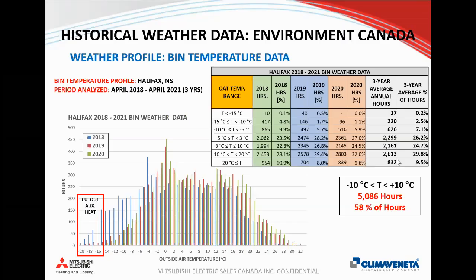This is now looking at Halifax, so on the East Coast. Their design temperature in Halifax is around -18 or so. And if you look at the number of hours that you're actually spending below -15 in Halifax, this past winter it didn't even go below -15 degrees Celsius outside. If you look at the years before, Halifax has milder winters, so it spends very few hours below -15 where you couldn't use some sort of heat pump technology.